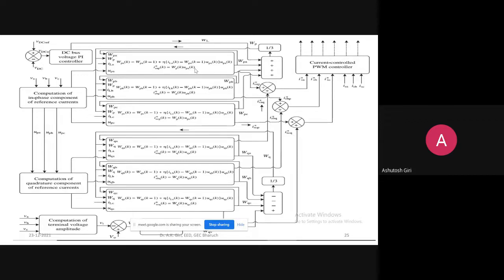Suppose you are injecting currents from the solar side, there should not be any injection of the reactive part, there should always be injection of only the active component from the solar side. Similarly, if we have connected any generator in the microgrid, the generator always supplies the fundamental component. If it is supplying the 50 hertz component almost in phase with the supply voltage, we can say it is supplying only active component to the microgrid.